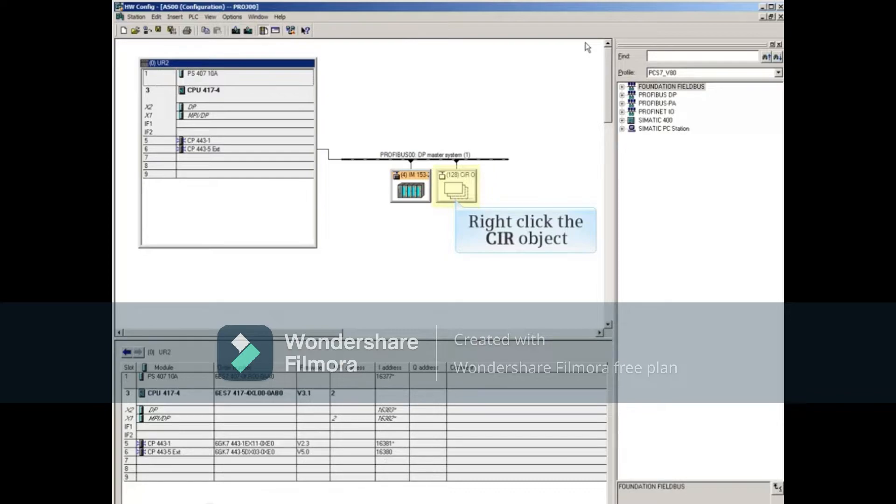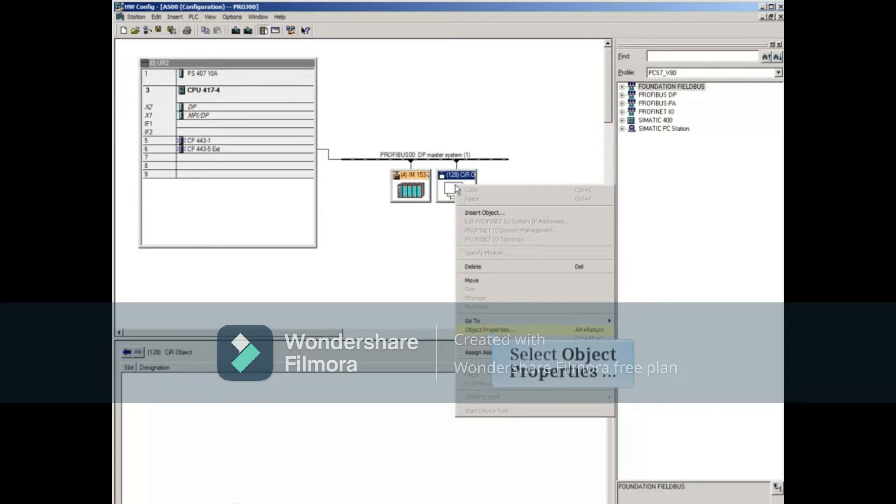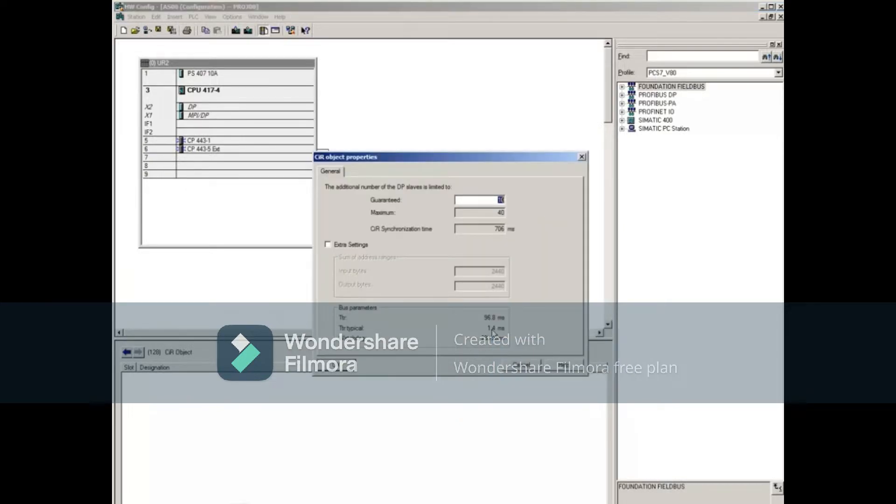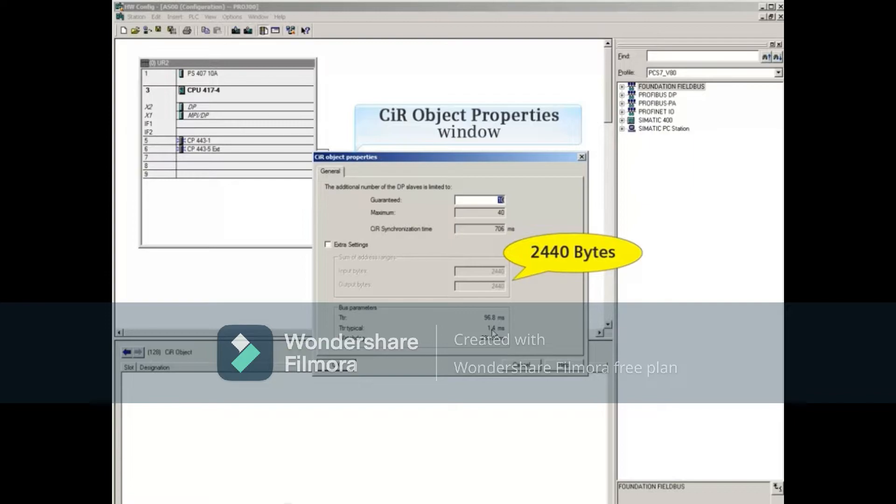Right-click the CIR object, and select the Object Properties menu choice. The CIR Properties shows 2,440 bytes of input and output memory, which guarantees 10 full ET200M racks.